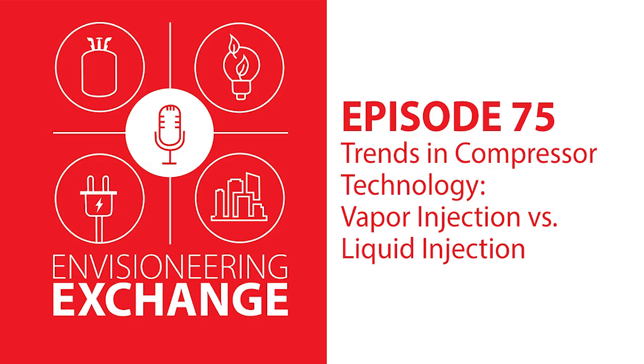Yeah, with liquid injection the only real benefit is that you're able to extend the map, as you said. The map is good in that it can run in colder climates now, with lower evaporating temperatures. It can meet the needs of cold climate heat pumps in most aspects, but you lose all the efficiency and capacity benefits that you get with vapor injection. So it's really just about system reliability for liquid injection. It is a simpler system, a bit more plug and play. A lot of OEMs choose that method because it's an easier path to market as a first initial concept. But most people are moving toward vapor injection nowadays.